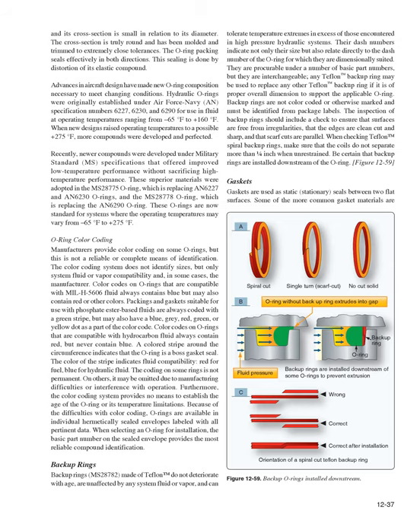Backup rings, MS-28782, made of Teflon, do not deteriorate with age, are unaffected by any system fluid or vapor, and can tolerate temperature extremes in excess of those encountered in high-pressure hydraulic systems. Their dash numbers indicate not only their size but also relate directly to the dash number of the O-ring for which they are dimensionally suited. They are procurable under a number of basic part numbers, but they are interchangeable. Any Teflon backup ring may be used to replace any other Teflon backup ring if it is of proper overall dimension to support the applicable O-ring.